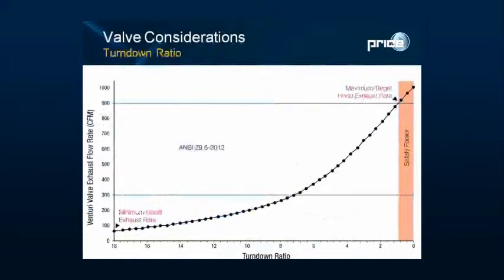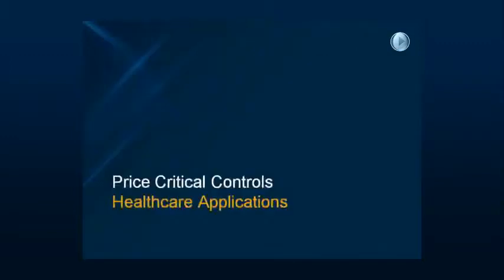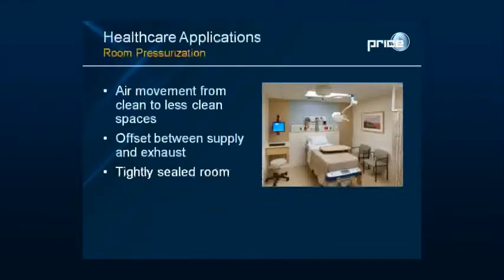Moving into healthcare applications, the primary concern is room pressurization. The goal is to have air moving from clean spaces into less clean spaces — positively pressurized rooms protect the patient, while negatively pressurized rooms protect others in the facility. Creating this differential pressure requires an offset between supply and exhaust rates, and a tightly sealed room envelope — the tighter the seal, the easier it is to achieve and maintain the desired differential pressure.